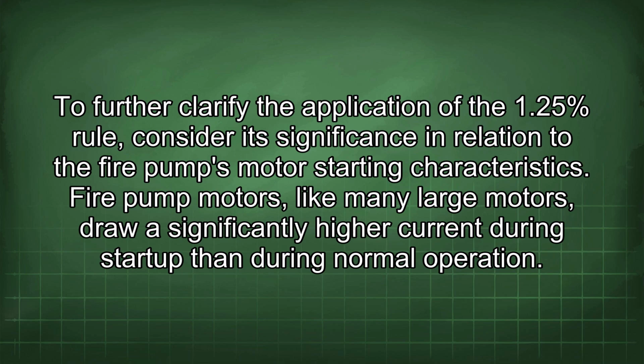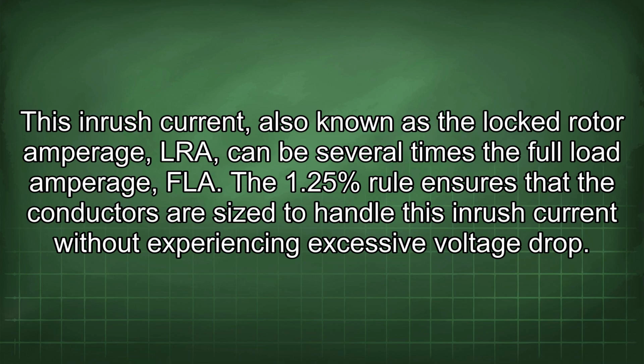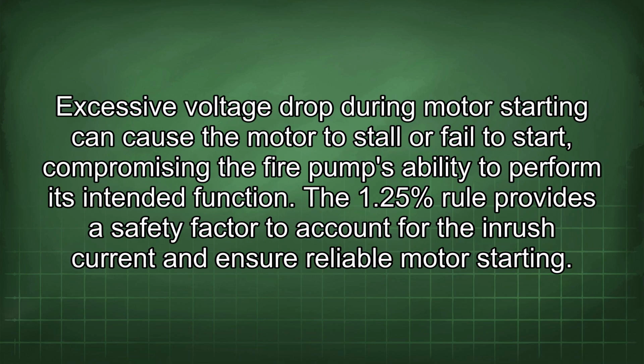To further clarify the application of the 1.25% rule, consider its significance in relation to the fire pump's motor starting characteristics. Fire pump motors, like many large motors, draw significantly higher current during startup than during normal operation. This inrush current, also known as the locked rotor amperage, LRA, can be several times the full load amperage, FLA. The 1.25% rule ensures that the conductors are sized to handle this inrush current without experiencing excessive voltage drop. Excessive voltage drop during motor starting can cause the motor to stall or fail to start, compromising the fire pump's ability to perform its intended function. The 1.25% rule provides a safety factor to account for the inrush current and ensure reliable motor starting.